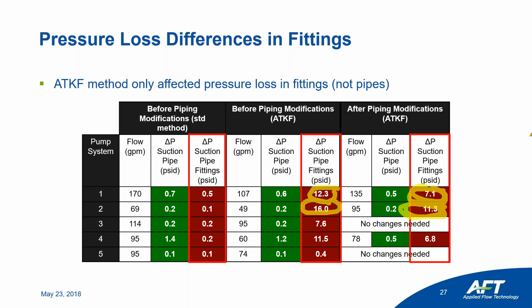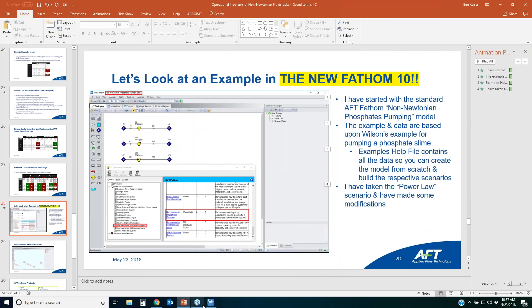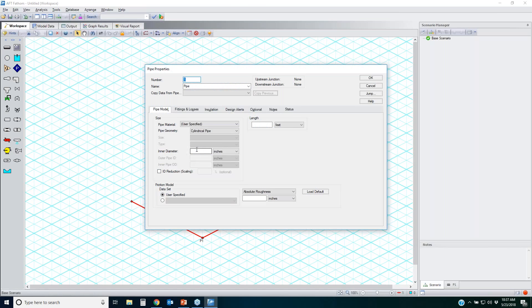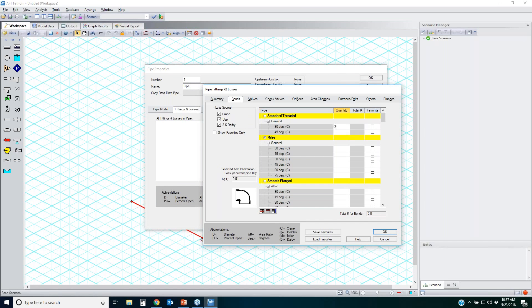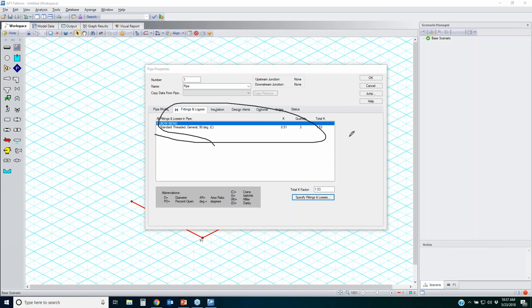Keep in mind the ATKF method only affects pressure losses in fittings, not in pipes. That said, if you lump pressure losses into a pipe itself and specify fittings and losses there, the ATKF method will still correct those pressure losses. So you can still account for correction factors on those losses when you lump fittings into a pipe — you don't always have to model junctions explicitly to account for corrections properly.